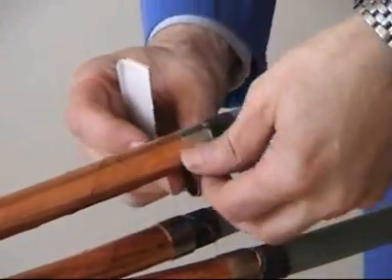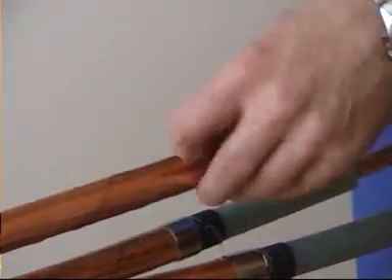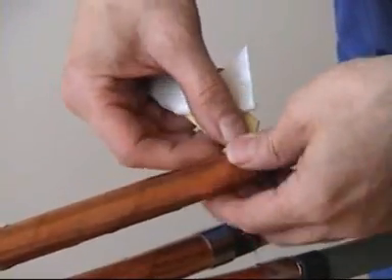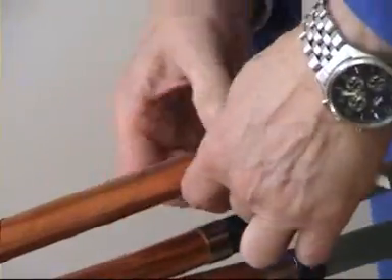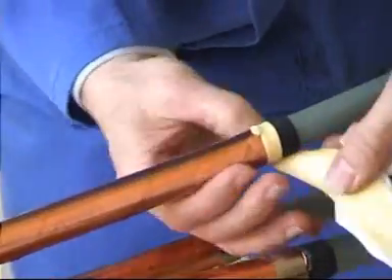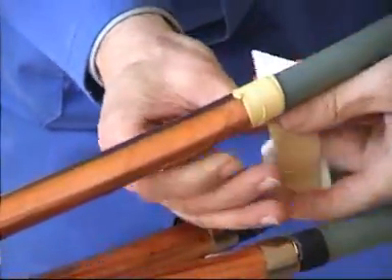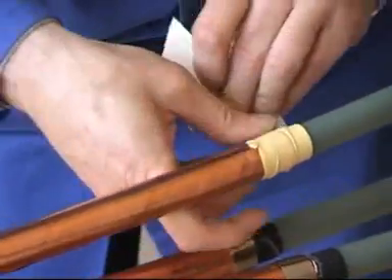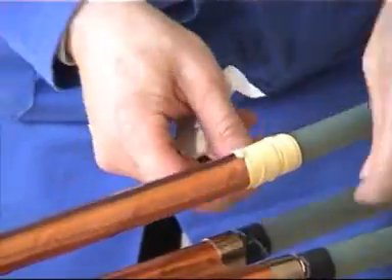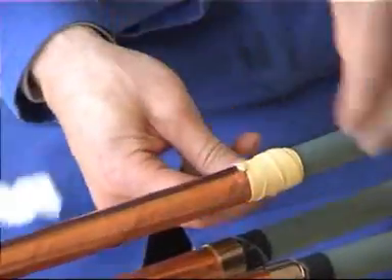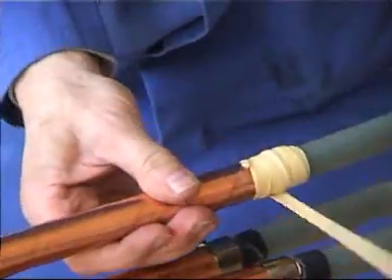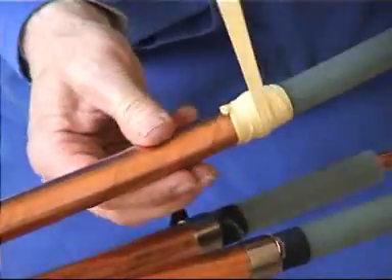Remove the remaining roll spring and with the yellow stress tape marked for screen ends, apply the tape with stretch and extend onto the copper tapes and primary insulation by 10mm either way. This will melt and flow into the screen cut at a later stage.